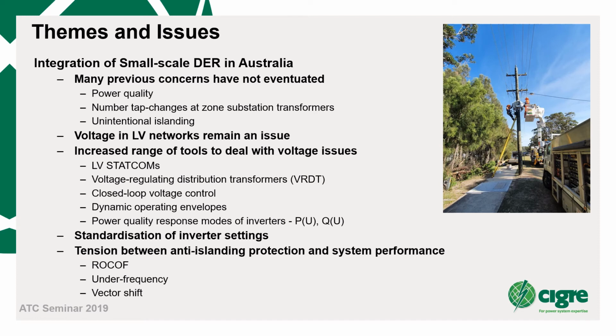In the remaining time left, I would like to touch on some of the issues that are of interest to C6 members, particularly relating to the integration of small-scale DER. Many of the previous concerns around this have not eventuated. This includes things like power quality, harmonics and flicker, number of tap changes at zone substation transformers, and issues with unintentional islanding. One aspect that continues to be a problem is voltage management in LV networks.